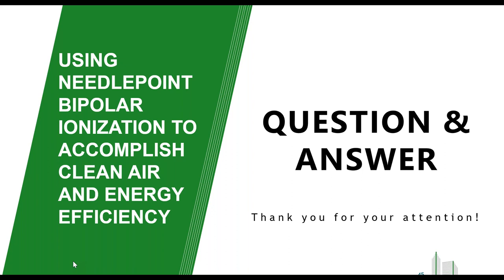We've done a lot of studies on other equipment through, you know, data gathering, and have found that ozone is a big problem in most of those technologies. Our technology in particular is UL 2998 listed, which means it's ozone free. But there are other technologies out there that can create positive and negative ions, but it does create ozone in doing so.